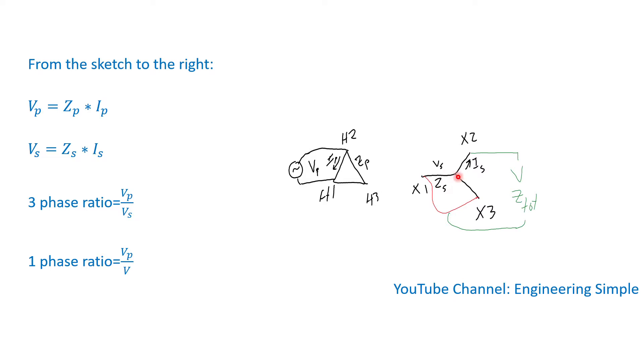Another way of performing voltage ratio measurement is the single-phase method. For the delta side, we can still measure the primary phase voltage. For the secondary, which is connected as a Y with the neutral not accessible, we short the terminals that we are not going to connect the test leads to. Then we measure the voltage — we'll call it V from one terminal to another.